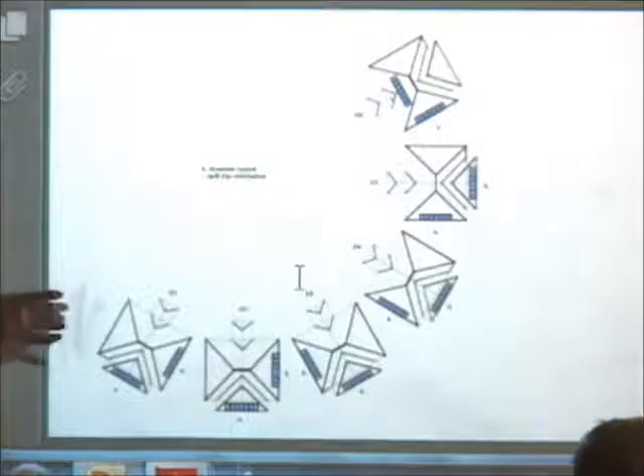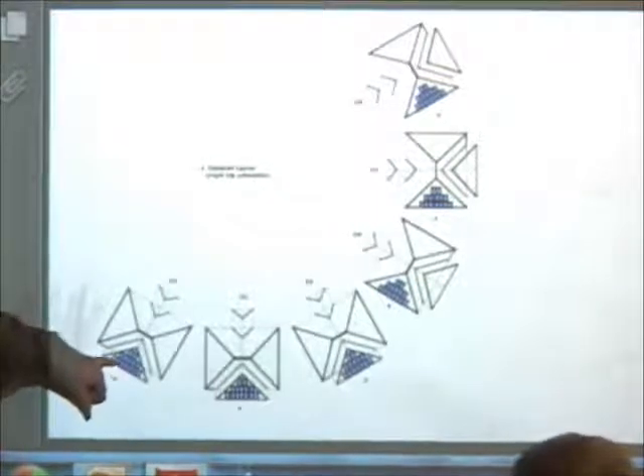That, you know, the energy that would be collected by this approach would be a pretty significantly reduced fraction of what might be happening in an optimum situation. So I suggested an alternate layout, which was a little risky, but it at least chose the facet of the roof that was most directly south. And I was able to just fit 14 modules on that hip roof component.